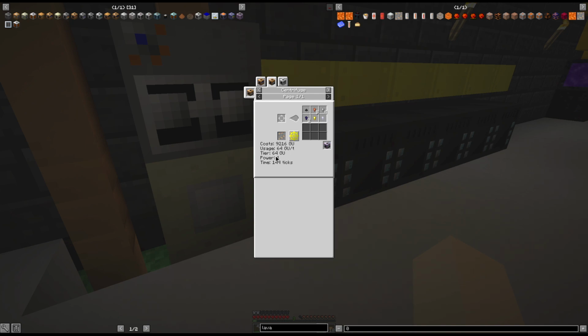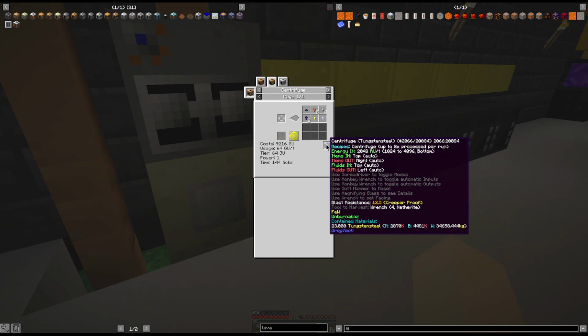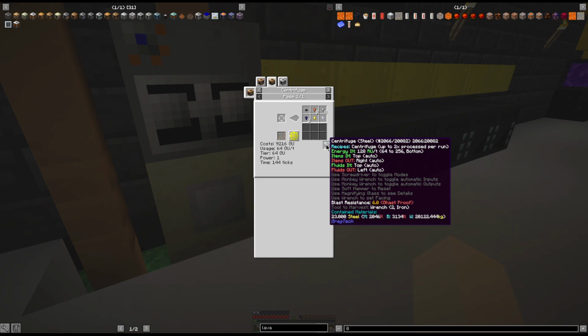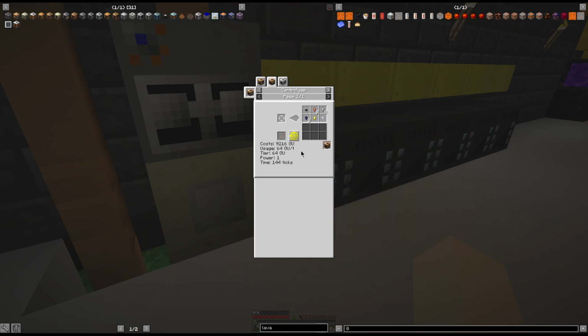But instead we did it at steel, because now we can take that steel up if we need to, to 128 or 256. The steel centrifuge can go from 64 to 256, and it does 2 processes per run, where the bronze only does 1. So it'll double up the process by doing it in steel.